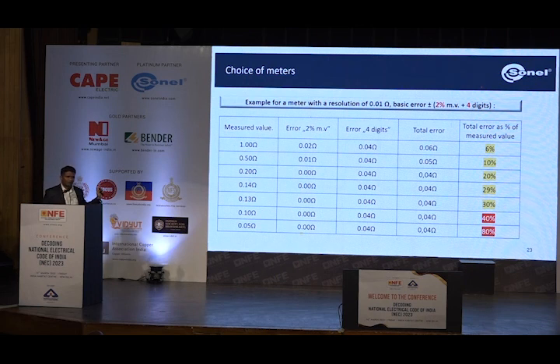Another important factor, since I come from the manufacturing side of this equipment: you might see manufacturers usually say the accuracy of the equipment is 2%. But please also look into the number of digits, because while making measurements in the low range, the digits could make a lot of difference.